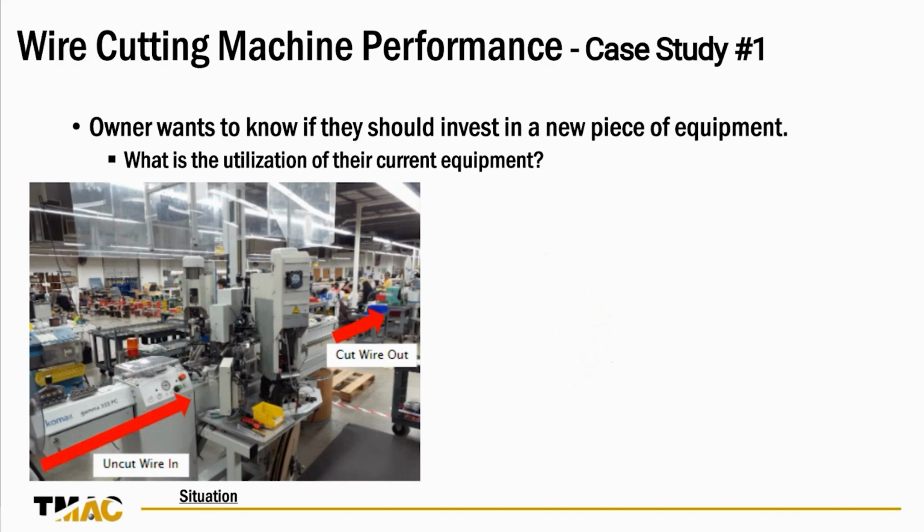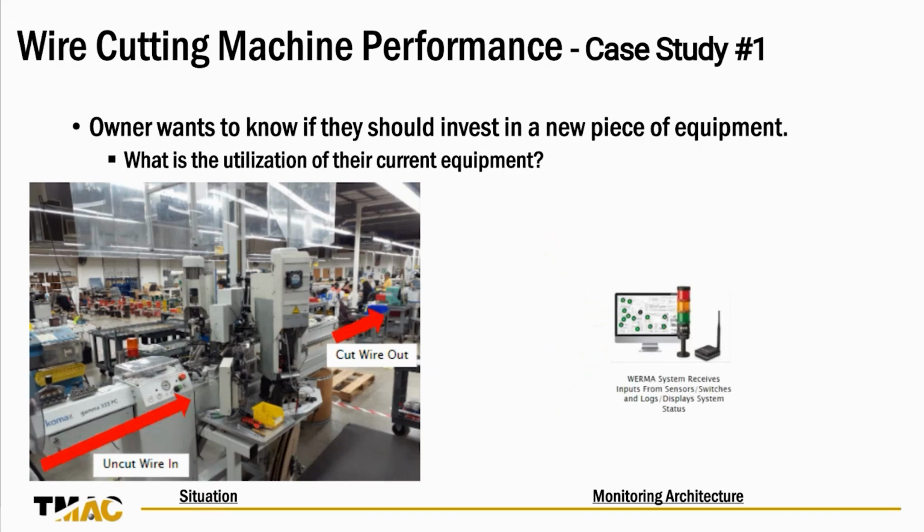So what we did is developed a monitoring architecture. This particular system we developed around a WERMA system, utilizing an operator-actuated downtime and setup button. This was a manual button that the operator would press, depending on the scenario. We used a distance-based laser sensor to detect a part inside this machine that rotated with the frequency of each part being produced, so we could use that to count parts.